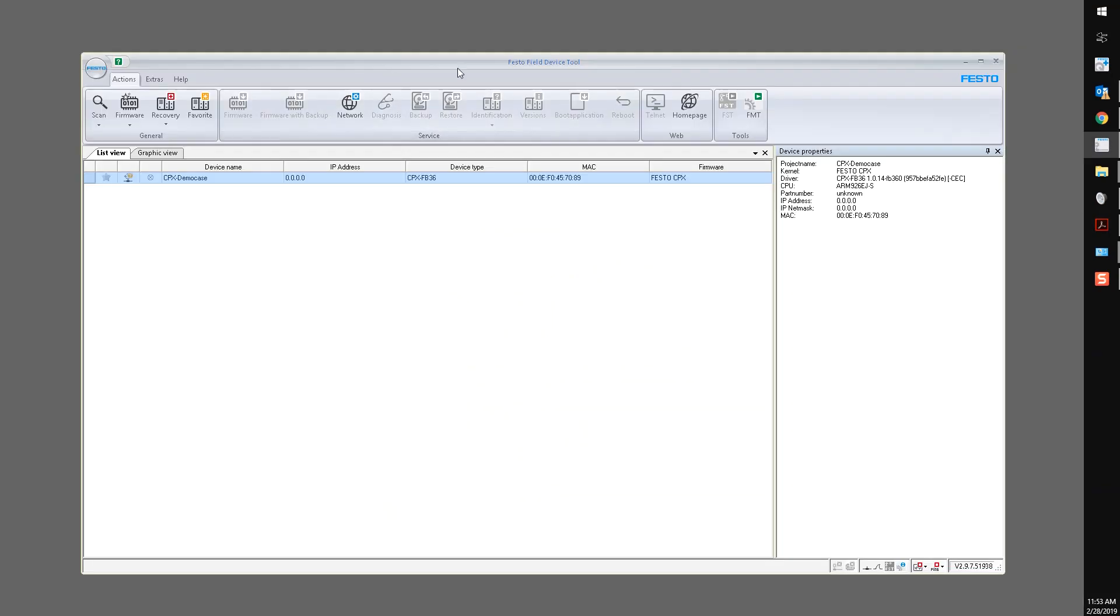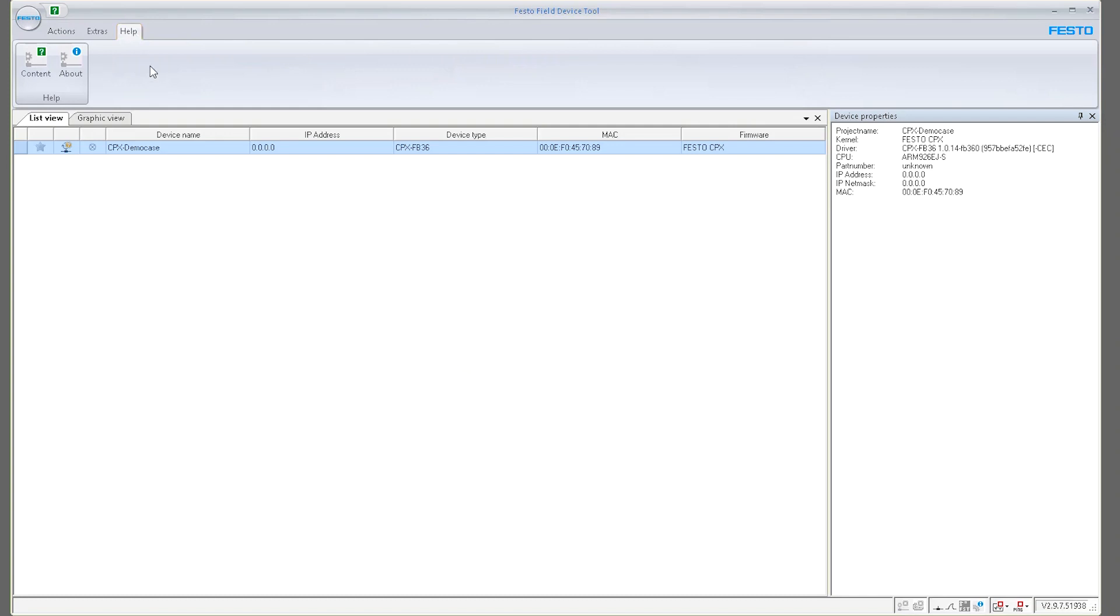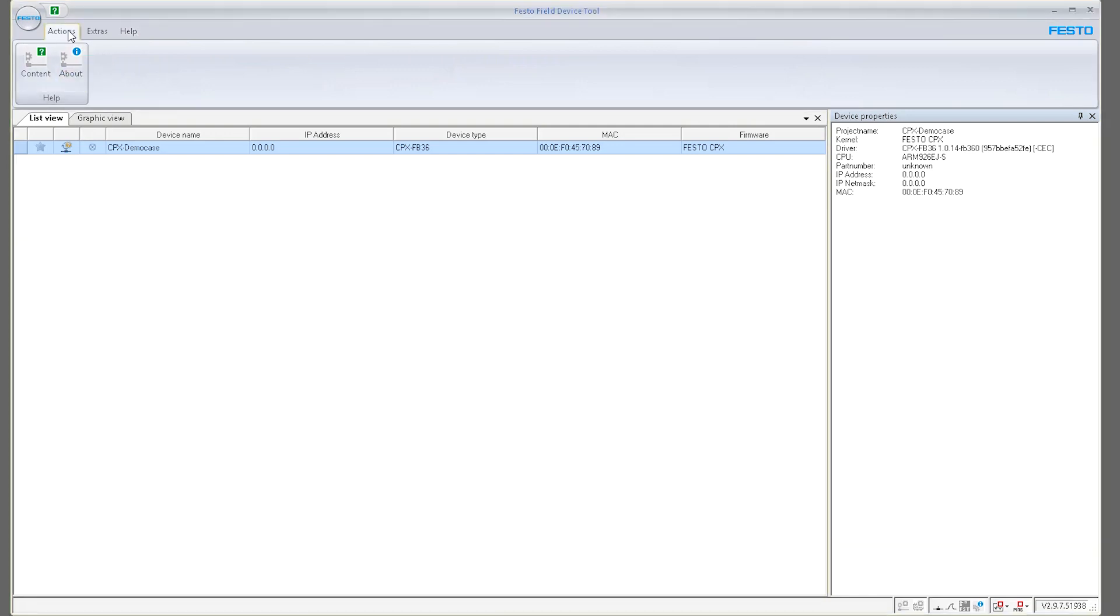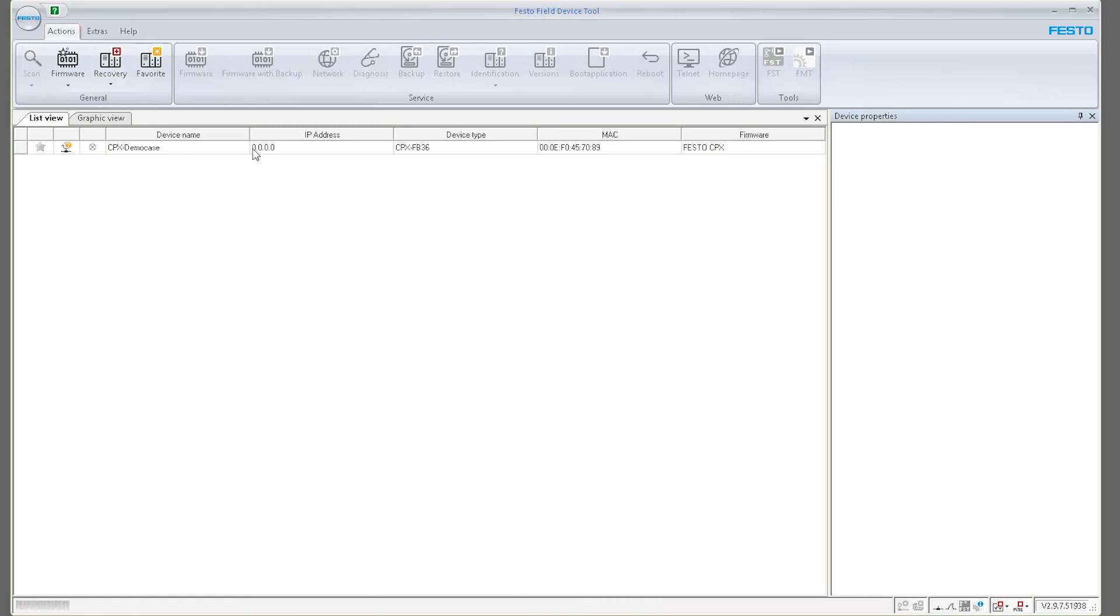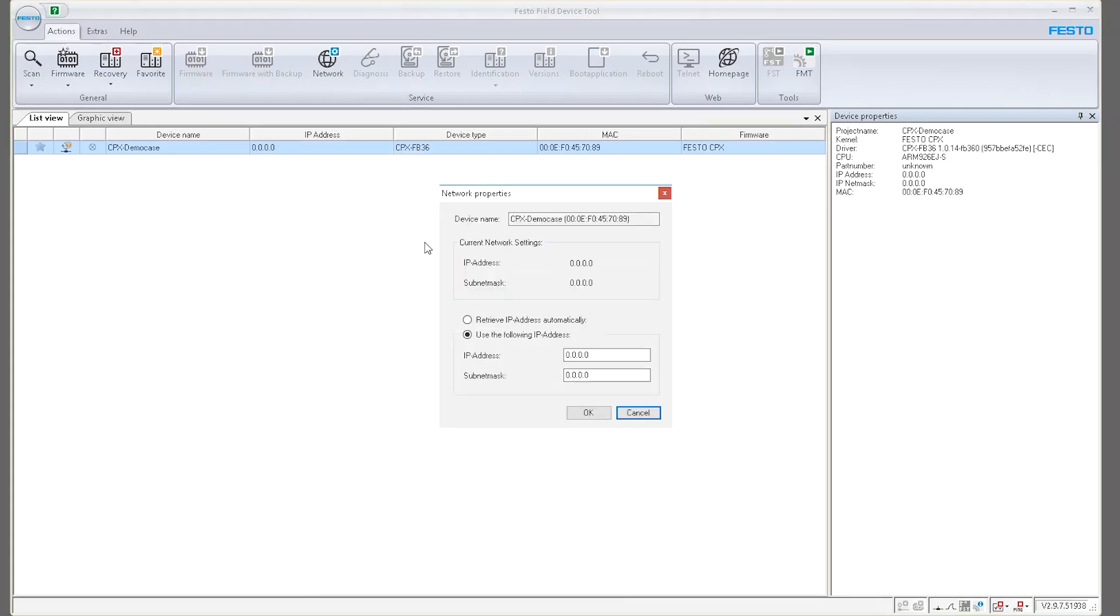So if I open this other software, which is called Festo Field Device Tool, this is the version that I'm using. I'm plugged in directly with an Ethernet cable right now to the device. I scan my network and I see IP address 0000. That's basically telling me that it's in DHCP mode.